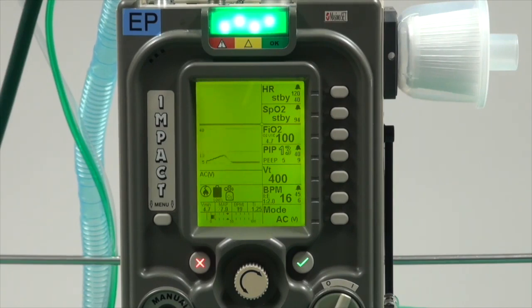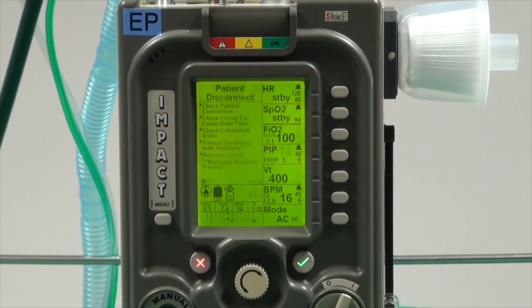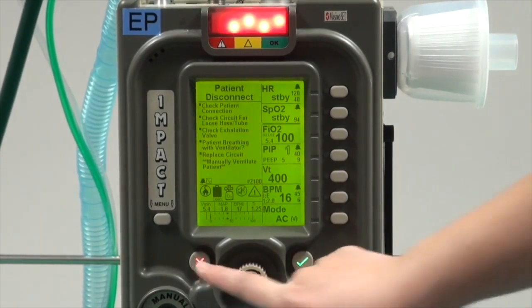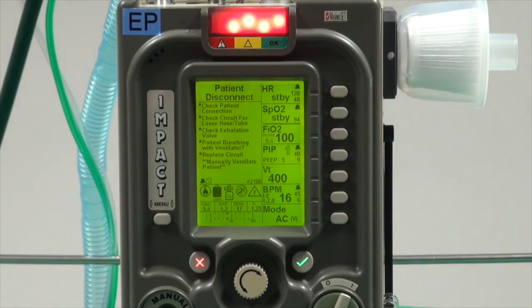Another possible alarm that might come up is patient disconnect. Do not panic. Press the alarm silence button. First, check whether the ETT is still connected to the ventilator circuit. Check whether your pressure and exhaust green and white lines are still connected to the ventilator. Once you secure all the connections, the alarm should go away.